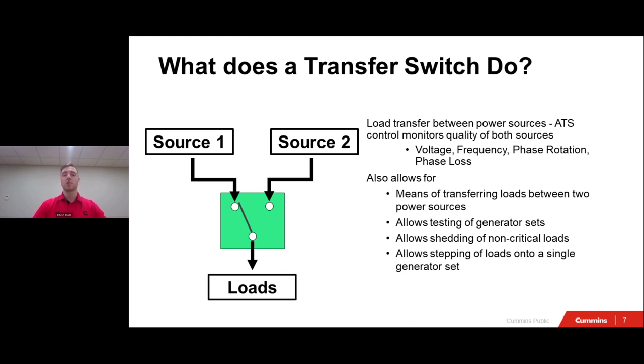So in an outage, the normal power source fails. And then next up, when the power from the generator or backup utility feed is stable and within the prescribed voltage and frequency tolerances, the transfer switch shifts the electrical load to the emergency power source. Depending on the facility's needs and preferences, that transfer either occurs automatically or is executed manually. When the utility power is restored, the transfer switch returns the load from the emergency power source to the normal power source. So going from that utility to gen, and then power comes back on, and then you switch from gen to utility. Once again, this can happen automatically or manually, depending on the type of switch being used in this operational mode.